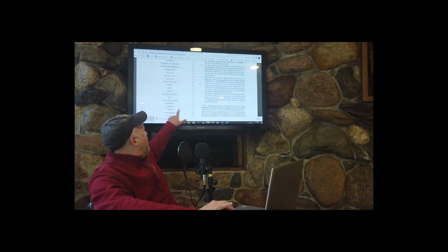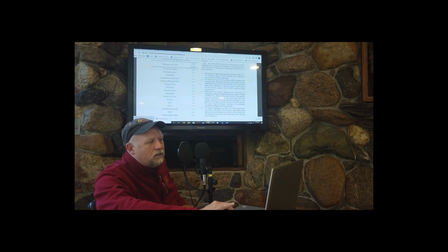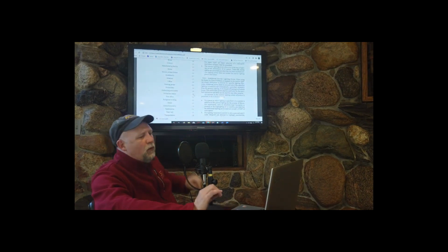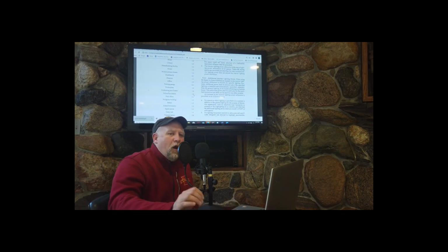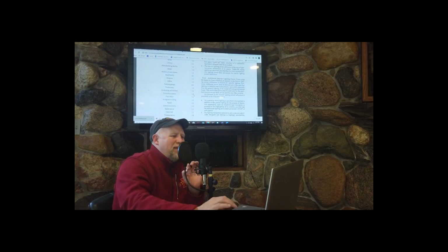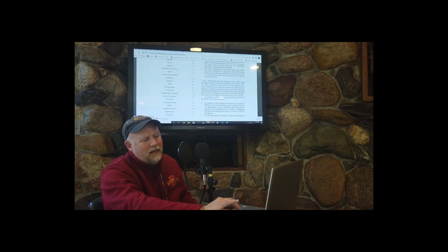Offices have a watts per square foot of about 1. Classrooms, let's see here. If we look at schools and universities, 1.2 watts per square foot. Our current energy code is just a slight bit lower than this. You'll have to ask Jenny what it is if she gets into it. Like I said, this is the 2007 version, so it's just a little bit out of date.